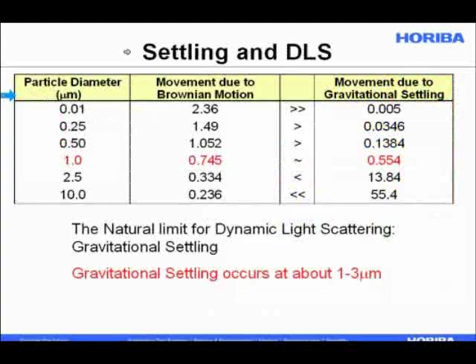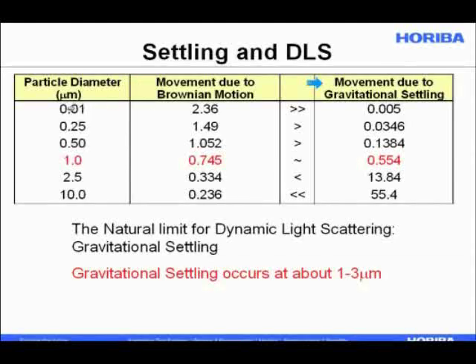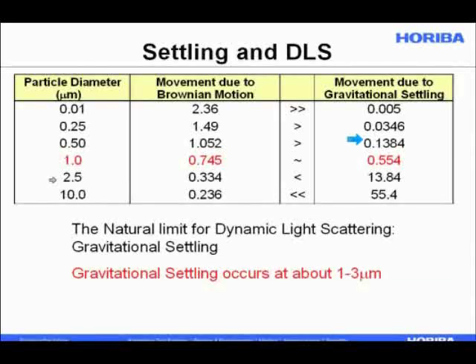A second practical consideration is settling. Dynamic light scattering works up to reasonably large particle sizes — many microns — but gravity is present and we're measuring particle motion. For a 10 nm particle, Brownian motion is much stronger than gravitational settling. Even at 500 nm, settling is not an issue. Above one micron, gravitational settling can become a problem — particles move in unintended ways during measurement, and they end up at the bottom of the cuvette, outside the measurement area. This is the natural upper size limit for dynamic light scattering.